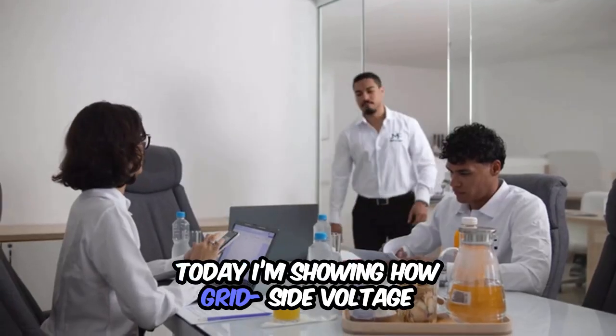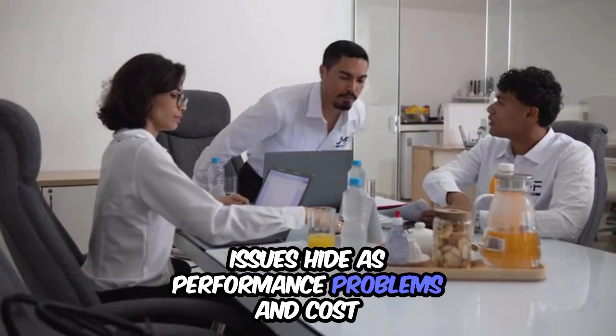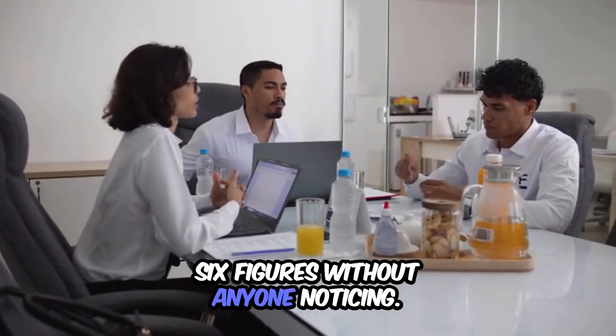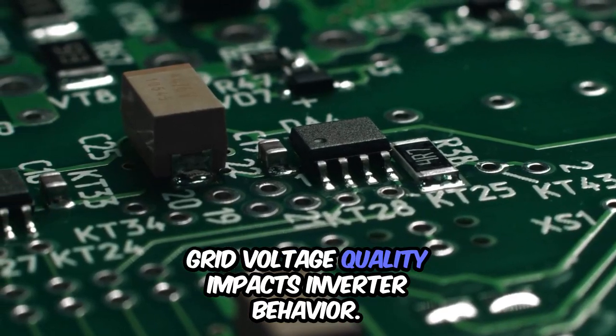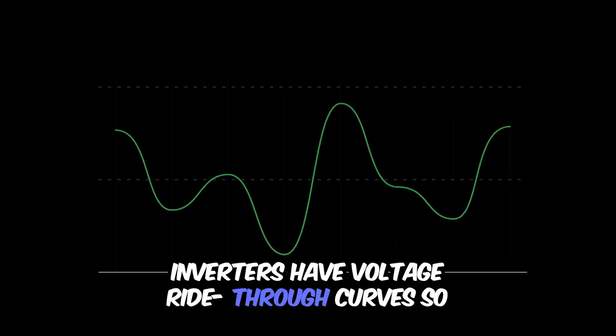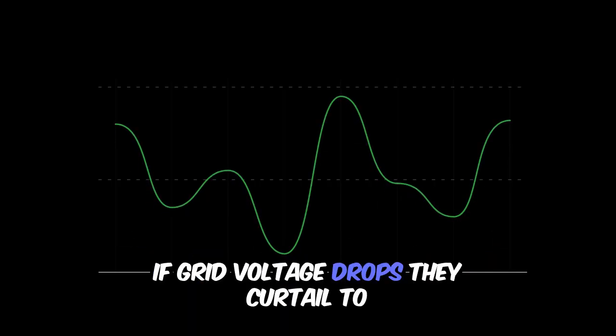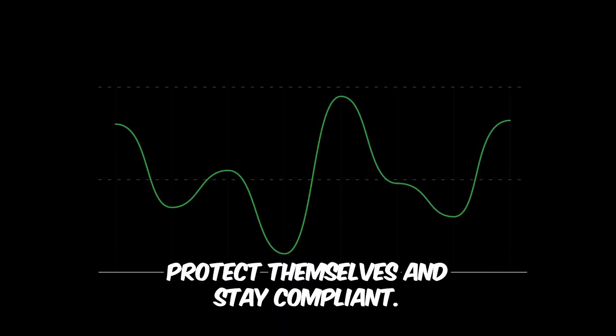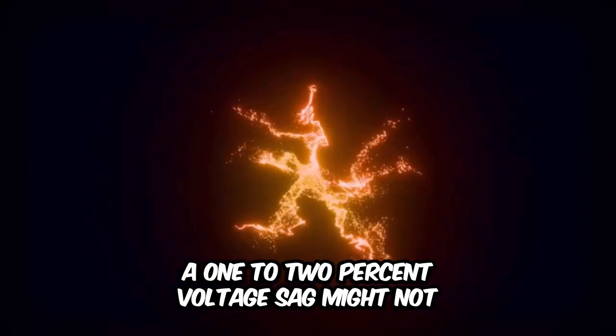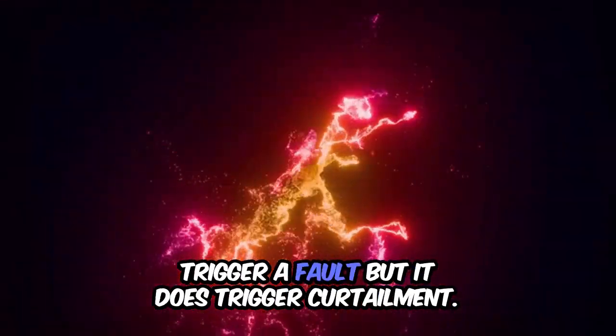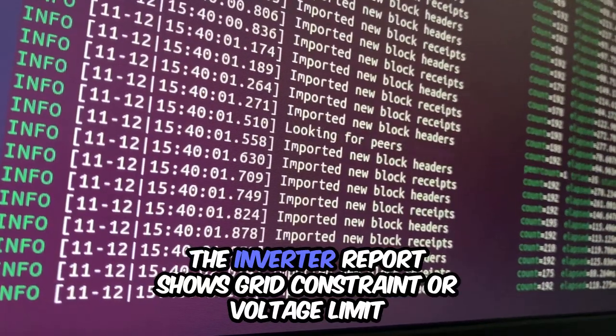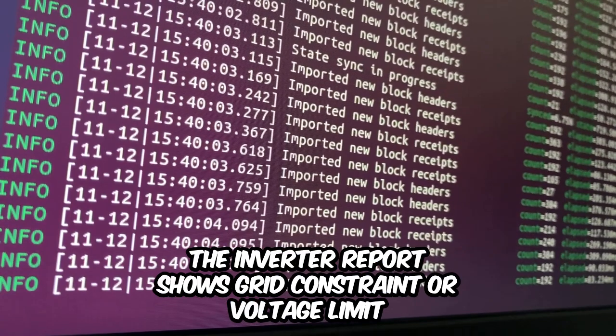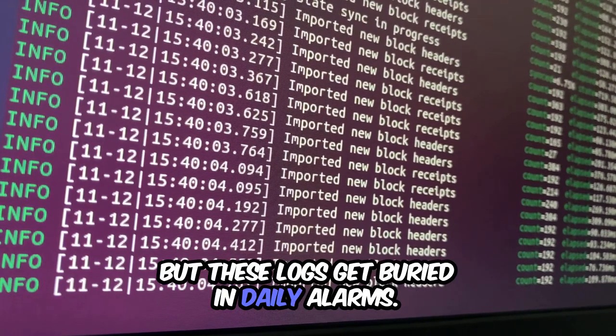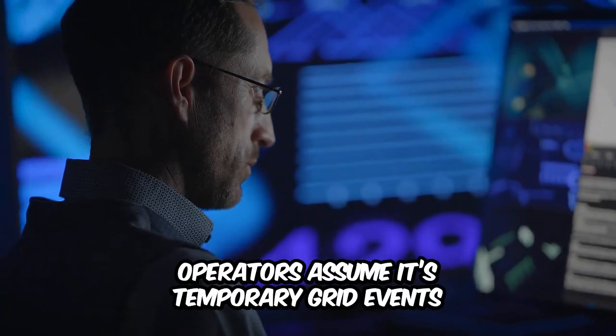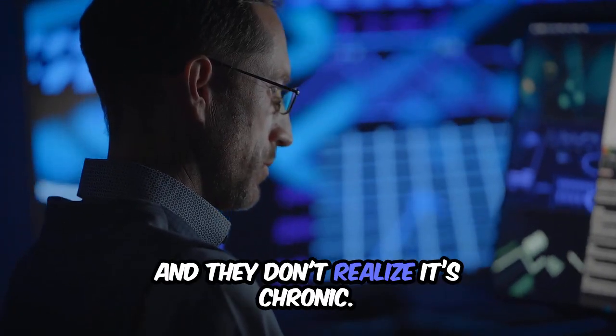Today I'm showing how grid-side voltage issues hide as performance problems and cost 6 figures without anyone noticing. Grid voltage quality impacts inverter behavior. Inverters have voltage ride-through curves, so if grid voltage drops, they curtail to protect themselves and stay compliant. A 1 to 2% voltage sag might not trigger a fault, but it does trigger curtailment. The inverter report shows grid constraint or voltage limit, but these logs get buried in daily alarms. Operators assume it's temporary grid events and they don't realize it's chronic.